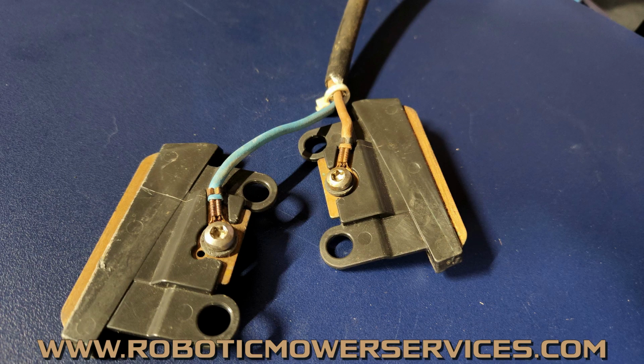You might want to start by cleaning some stuff up, or just replace that assembly in general. Something to look at is those wires that screw onto those plates. Those plates can become corroded, and you can get rust buildup in there. Take that screw out and make sure everything's clean. That can make a big difference in the amount of resistance you have in that little harness.